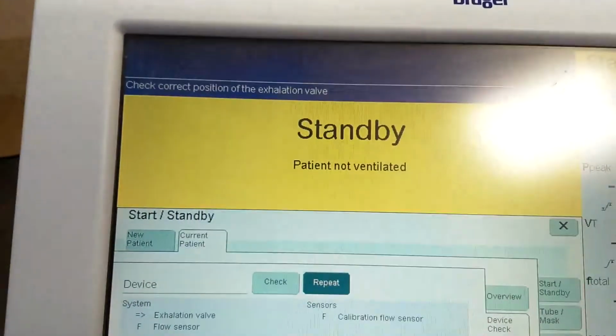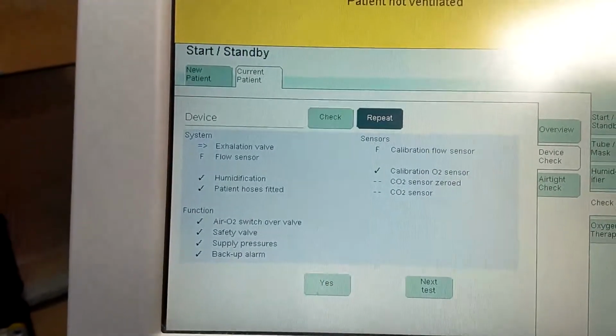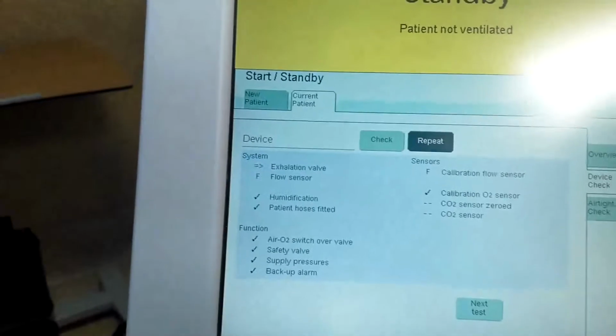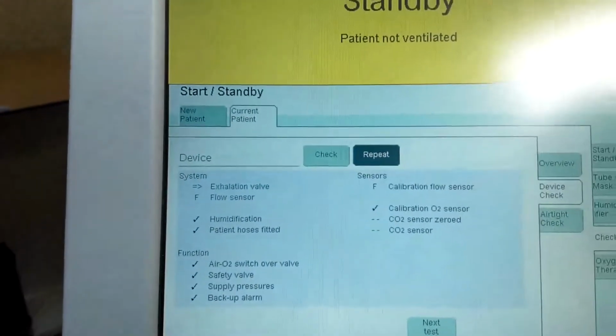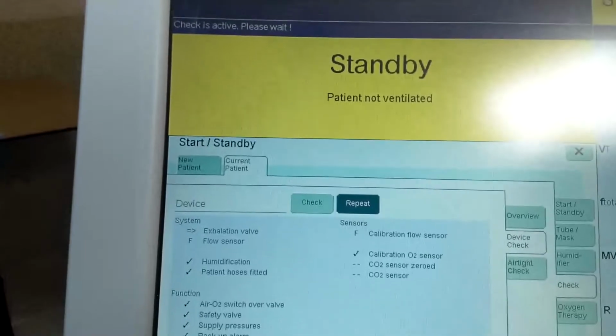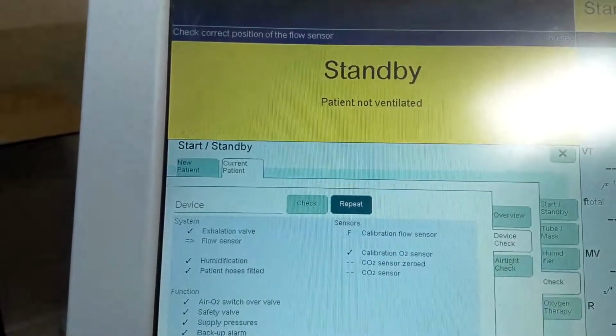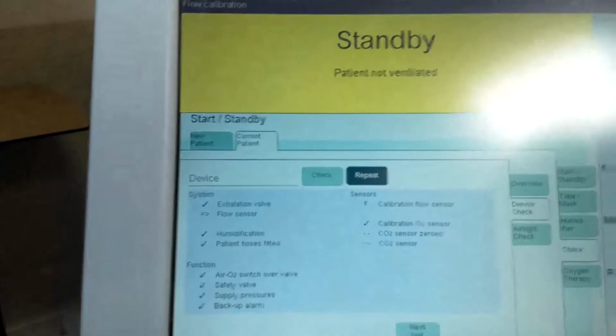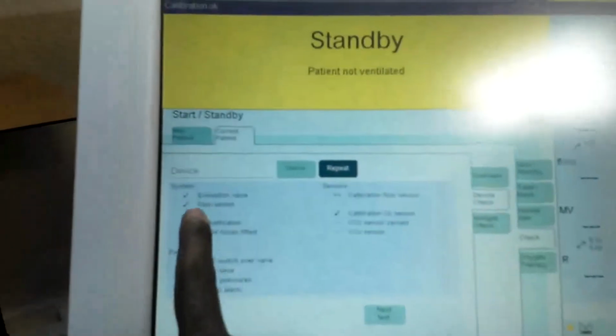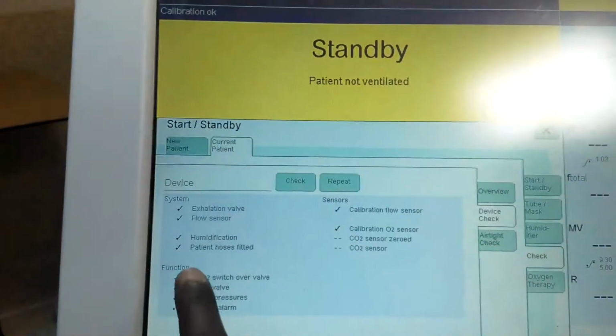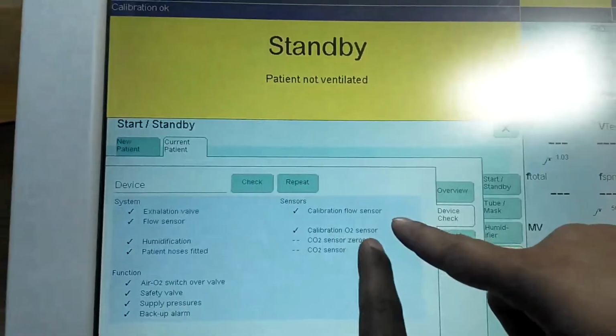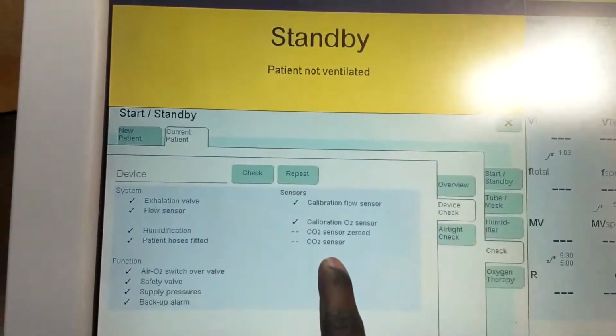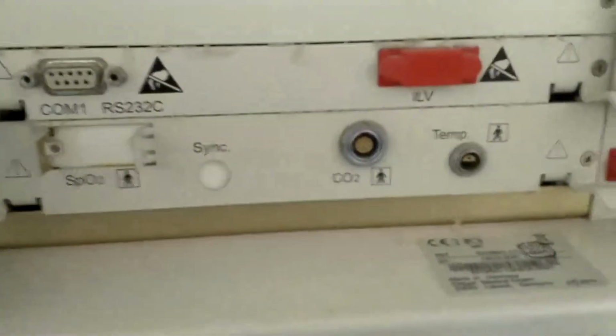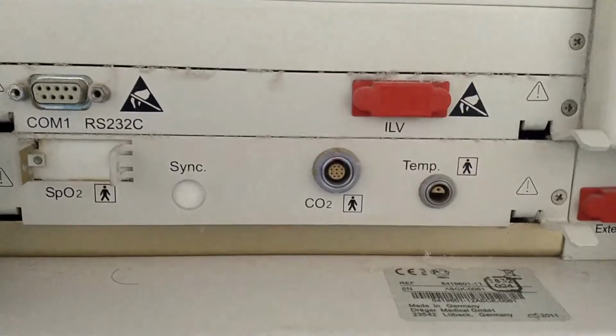Okay, check the correct position of the exhalation valve. Yes. Connect test line. Yes. Correct position of the flow sensor. Yes. So these two tests, which failed previously, have passed, and even the calibration of the flow sensor has passed. So all the tests passed, except the CO2 sensor, because the CO2 sensor is an optional feature to measure the end tidal carbon dioxide.